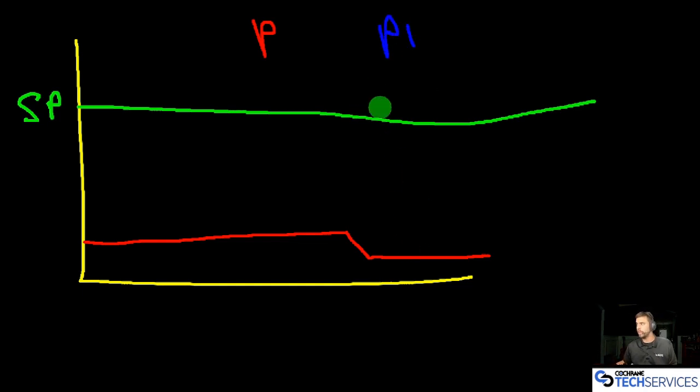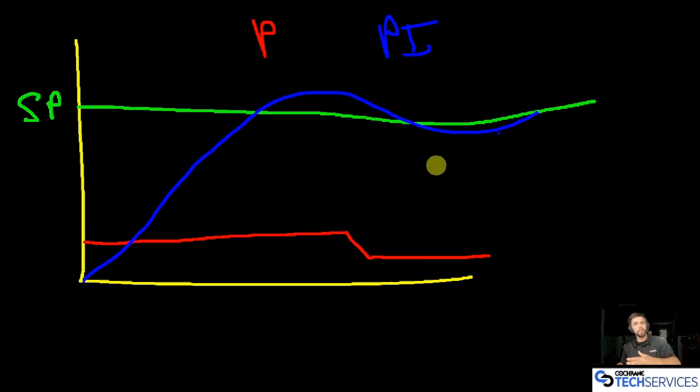Where if we used PI control, oh, ho, ho, we would probably get to set point rather quickly, and we would kind of oscillate around it just for a moment, and we would settle at that set point, whatever our space temperature set point was. And it'll actually maintain that. Even as space temp changes, it'll auto-correct itself. That's why the integral is so important. It allows that auto-correcting function of a PID control loop.